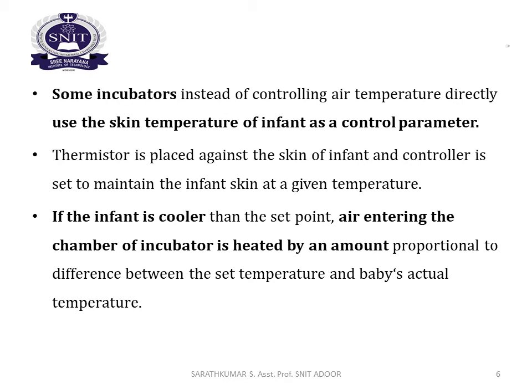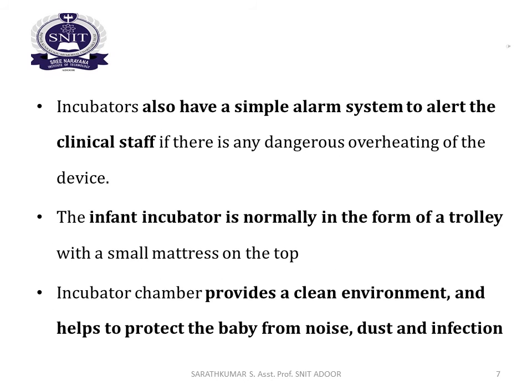If the infant is cooler than the set point, air entering the chamber of the incubator is heated by an amount proportional to the difference between the set temperature and the baby's actual temperature.